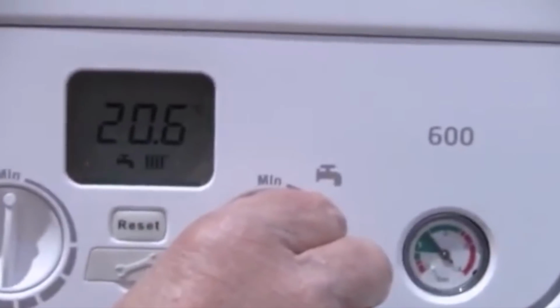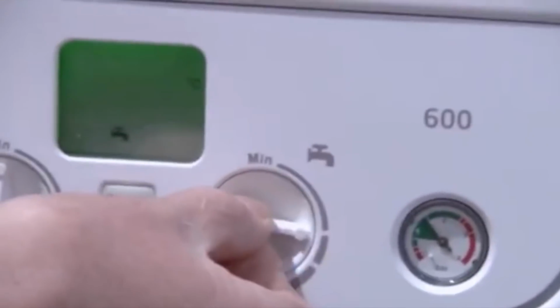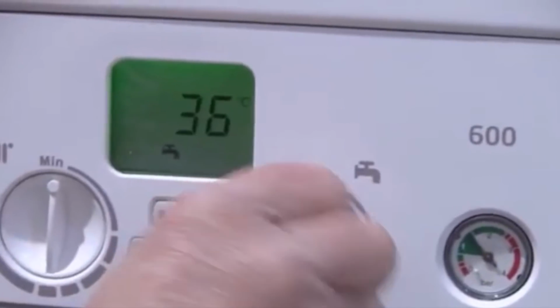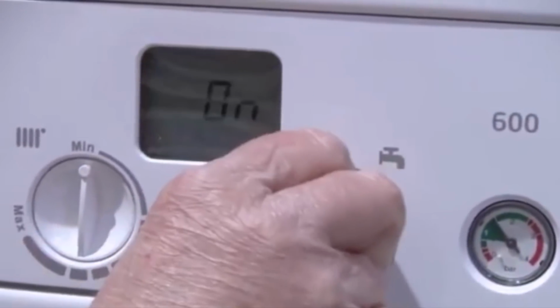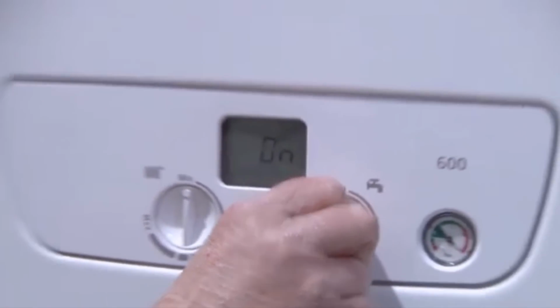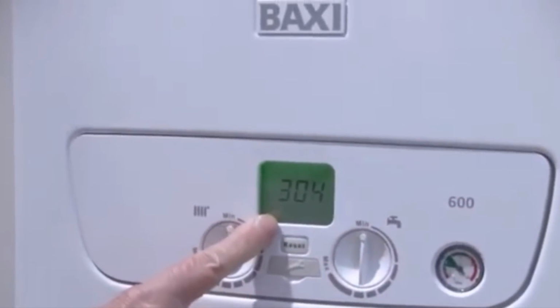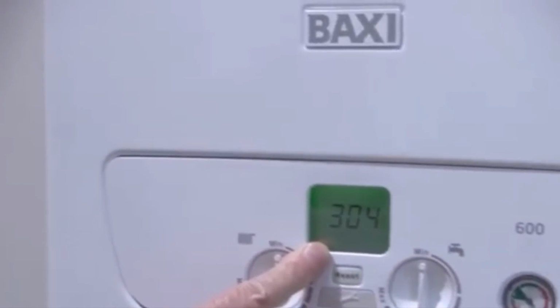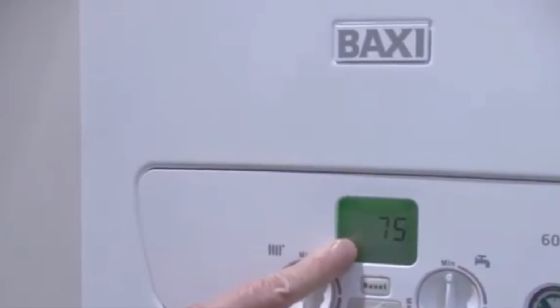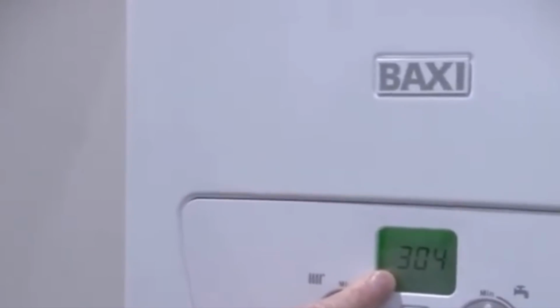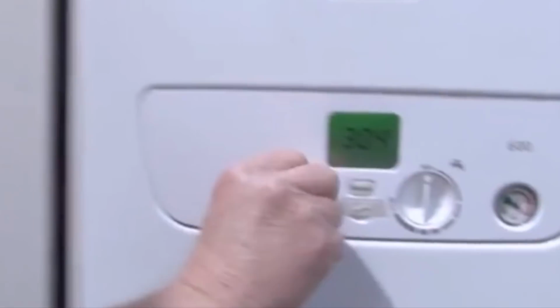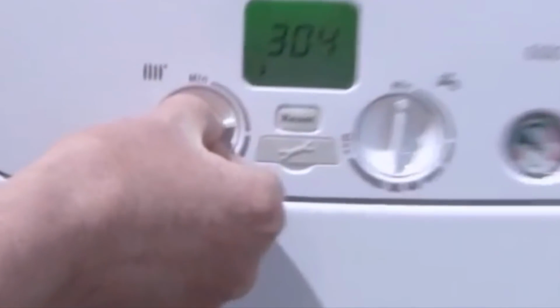Now, to flue gas analyse this boiler, you'll have to put both control knobs to minimum, then with the hot water control knob, 2 quick quarter turns will then turn the boiler on, and then put it in chimney sweep mode, which is 304. You can then use the central heating control knob to go between minimum and maximum for the fan speed to be able to do your flue gas analysing.